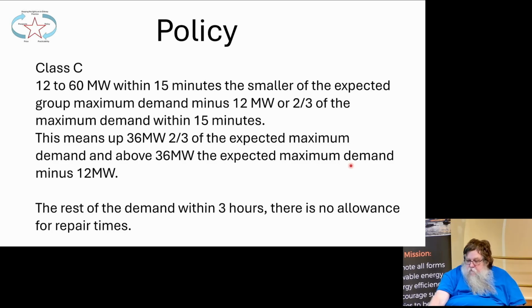So when we get above 12 megawatts, we go to Class C. So 12 to 60 megawatts within 15 minutes rather than 3 hours. The smaller of the expected group maximum demand minus 12 megawatts, or 2/3 of the maximum demand, has got to be restored within 15 minutes. So 15 minutes is too quick to rely on guys getting in their cars, driving out and looking in substations and operating switches. It's got to be done automatically or remotely, and sometimes it's one or the other, sometimes it's both together.